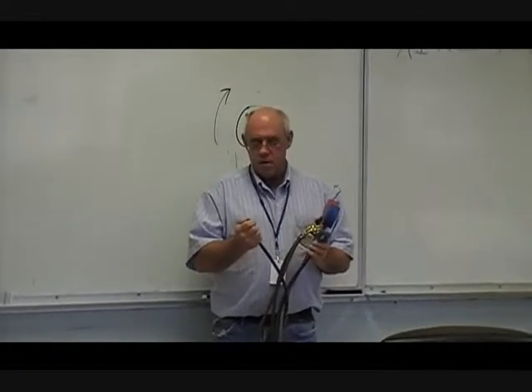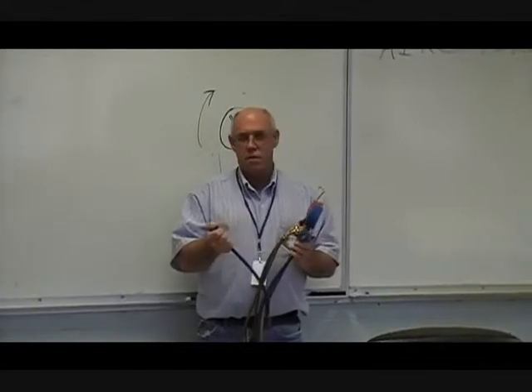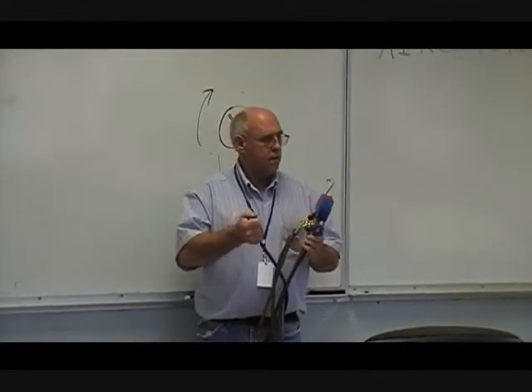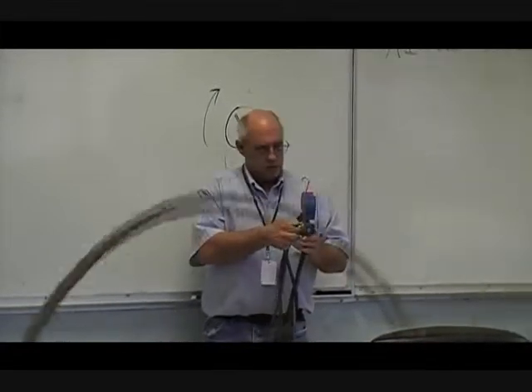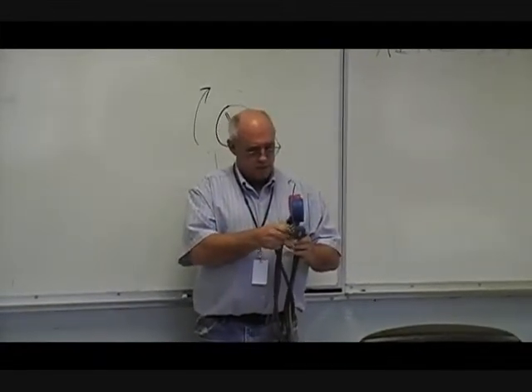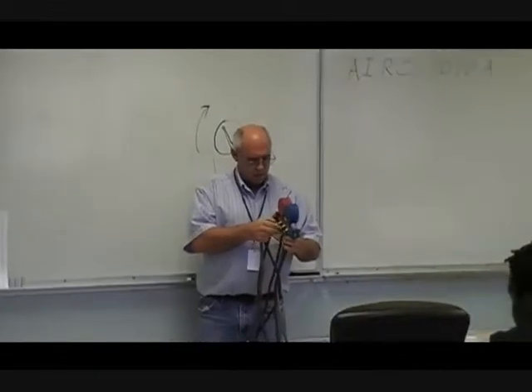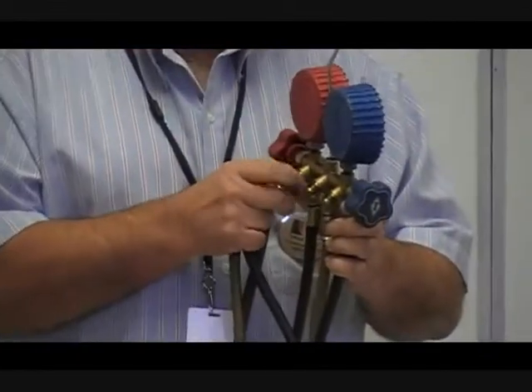If you hook this up on a system, it's going to get oil on. The refrigerant and the oil flow together. So you're going to get oil on this. If these lines are not parked properly and are allowed to dangle, I just want to show you what can happen. I don't want anybody on my job doing this because it may not create a problem at that particular time, but it will later on. I have seen this, folks. A fellow comes in, throws that behind him, and he's walking across the yard. Now, you tell me, what's going to get in those hoses?